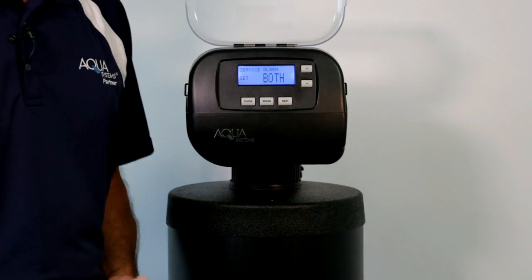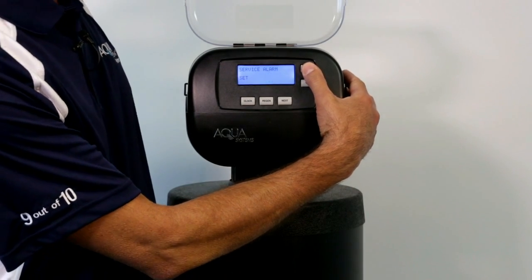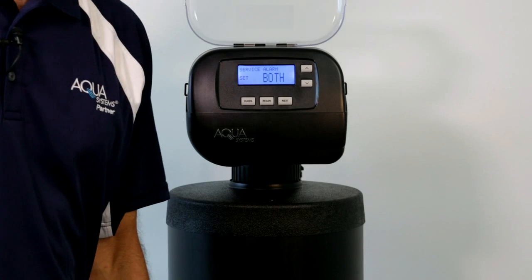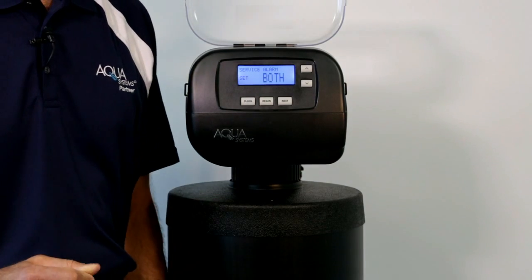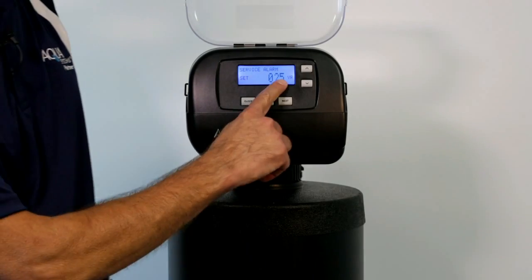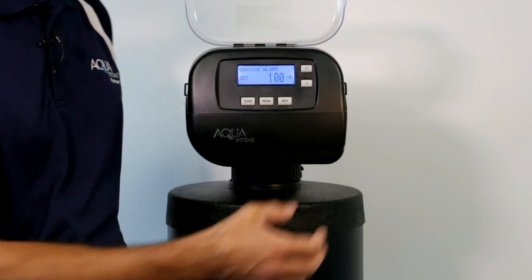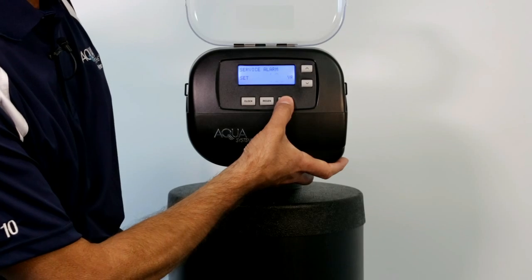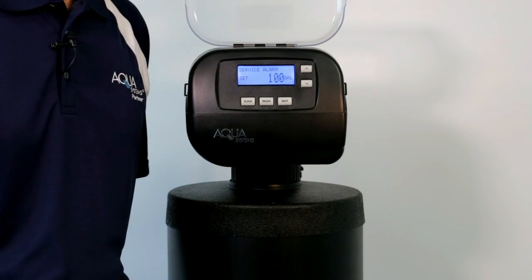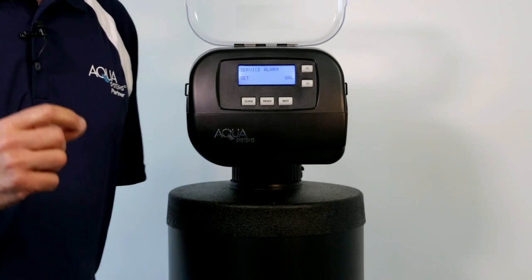Now on this screen it's currently saying both. This will allow me to demonstrate how you can set it to either being off, on time, on gallons, or both. Both refers to both time and gallons. So that's the example we're going to use here. If you choose both and then you press next, it allows you to first set the period of time, and you can set that based on quarters of a year in segments. And then after you set the time, it allows you to set the gallons. And you can set a gallon range to trip the service alarm after that number of gallons has been reached.